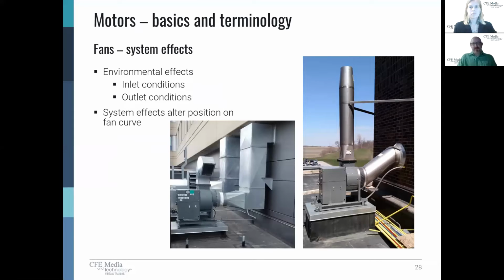System effects. This is what allows us to determine whether or not we're using our power effectively. So on the photo on the left, we see 2 hard 90s coming into a fan. Now, I can tell you personally, this is a noisy and a terrible arrangement, and you shouldn't do this. The image on the right is what you should be aiming for, a nice smooth transition.